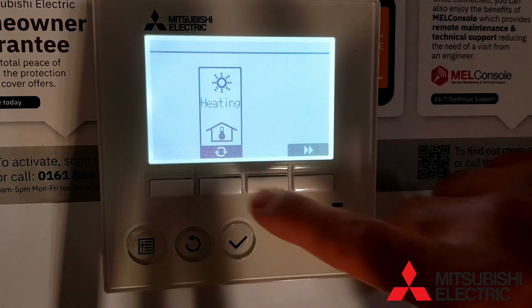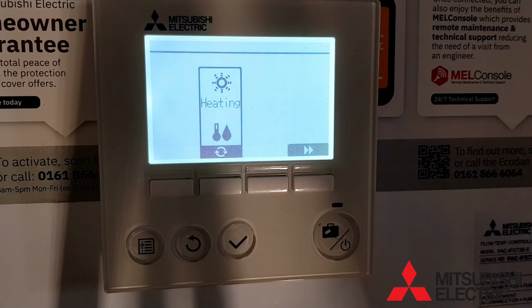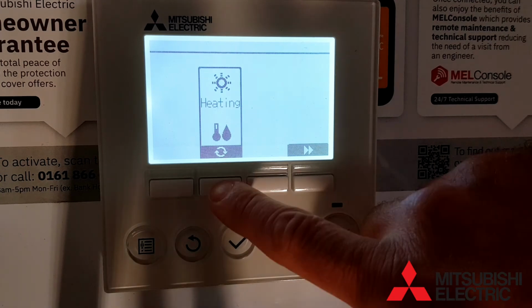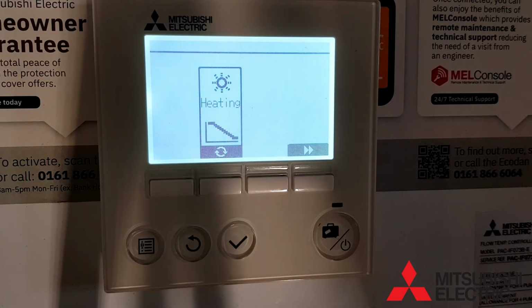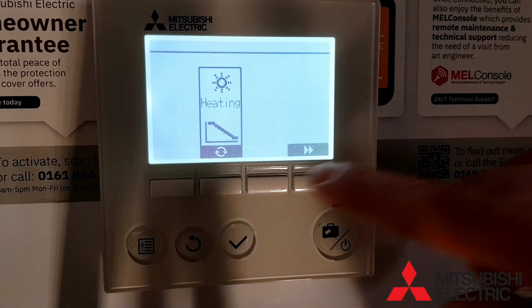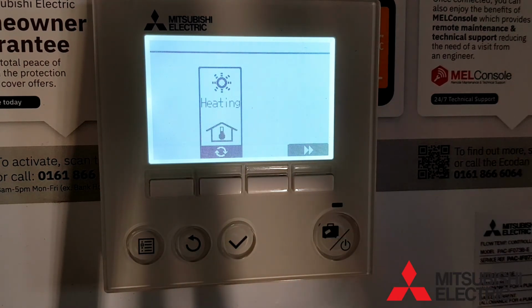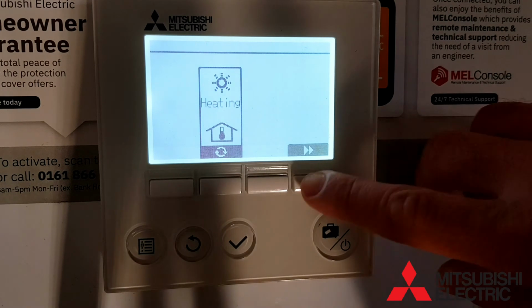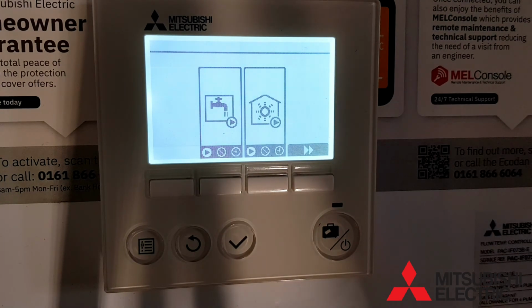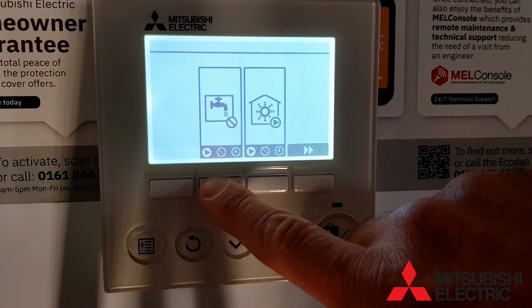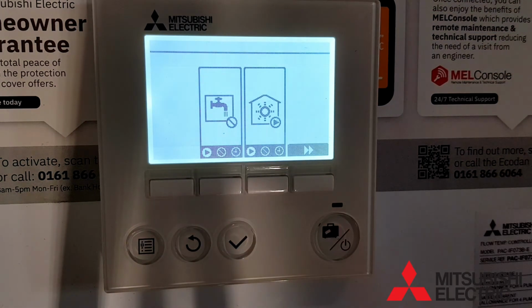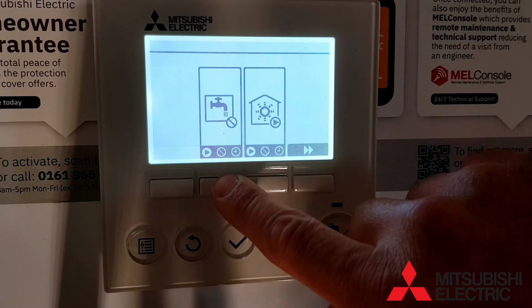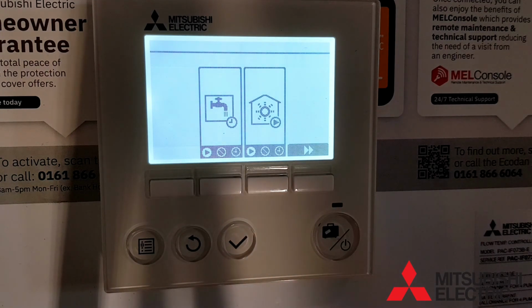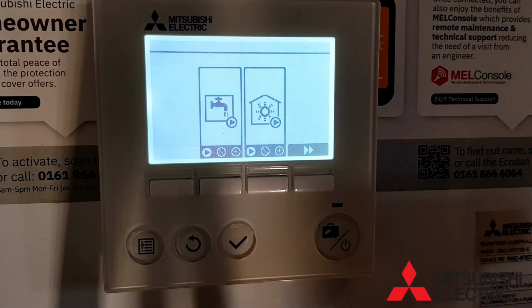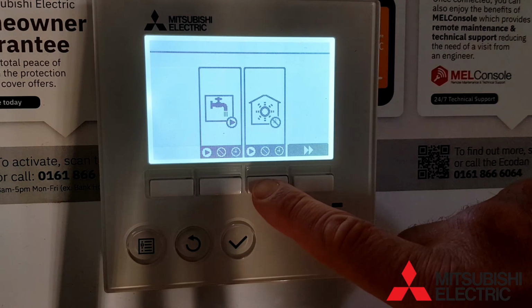The wizard will now take you through to the heating settings. We have the room adaptation mode, fixed flow temperature, and the compensation curve mode. Press the forward button to move to the next screen. This is like a 2-channel time clock function. You can have it off, on timer mode, or constantly on, which is the arrow symbol. You have the same options for both hot water and heating.